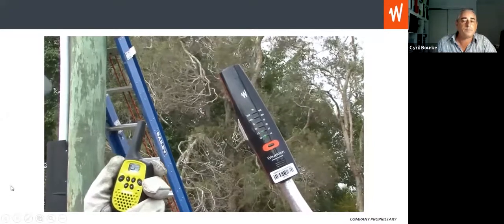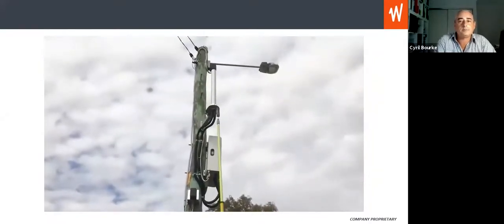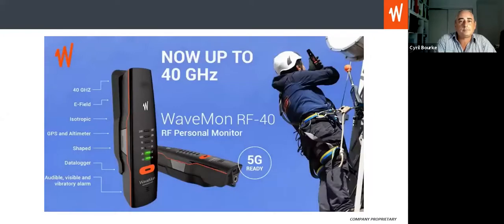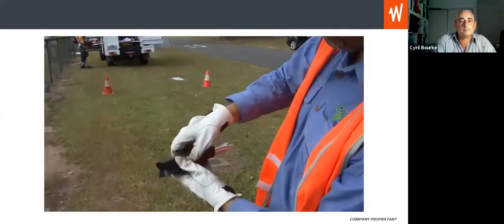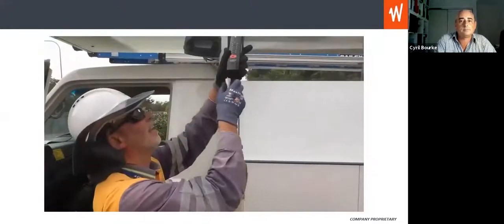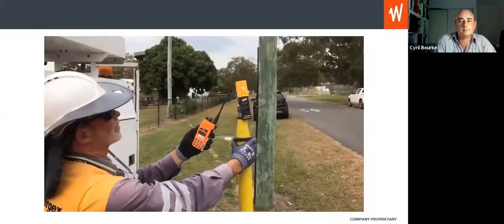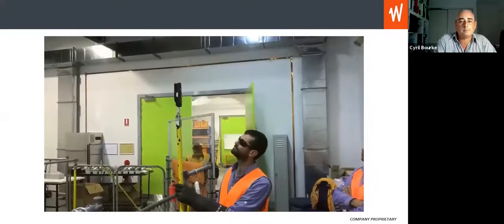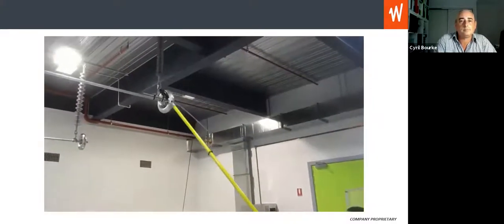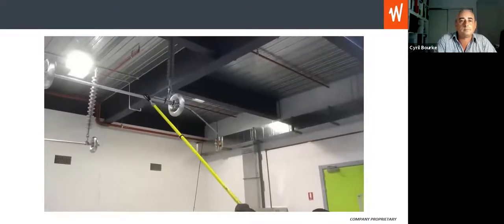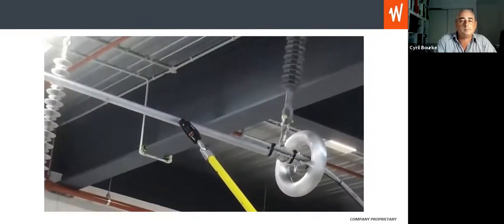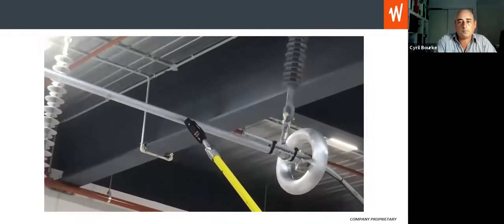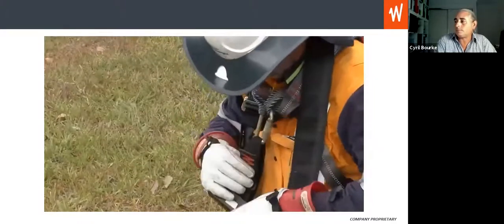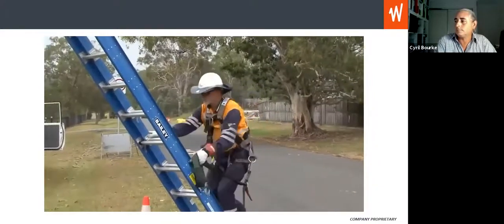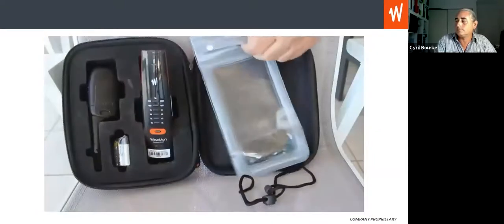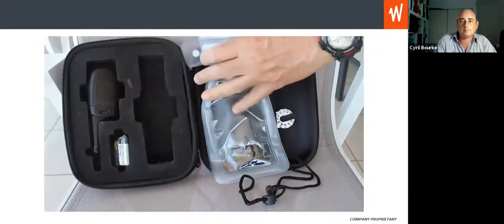At EQL, we use the WaveMon RF40 personal monitor to alert our workers when working near RFR fields. The WaveMon RF40 is 5G ready and measures up to 40 gigahertz. A key feature of this monitor is that it can be attached to sunrise fittings on operating or telescopic sticks. The performance of the RF40 monitor was superior to others trialled. It didn't false alarm in proximity to energized 11 kV conductors, whereas the others did. Further testing indicated the RF40 did false alarm, but only when directly touching energized 22 kV and if placed within 100 mm of energized 33 kV apparatus. Since the monitor is worn on the arm or harness, it should never come close enough to false alarm. Even when worn by linesmen, the monitor has a water-resistant rating, but can be further protected by placing it in the provided weatherproof pouch.